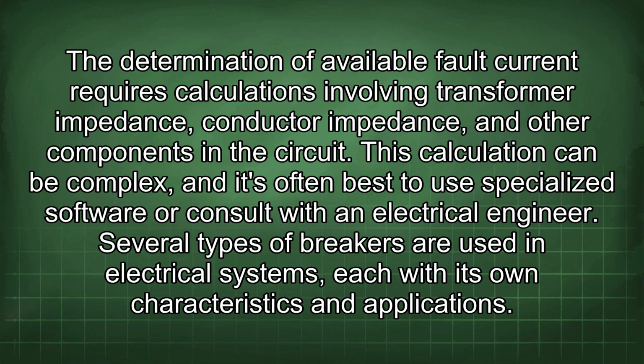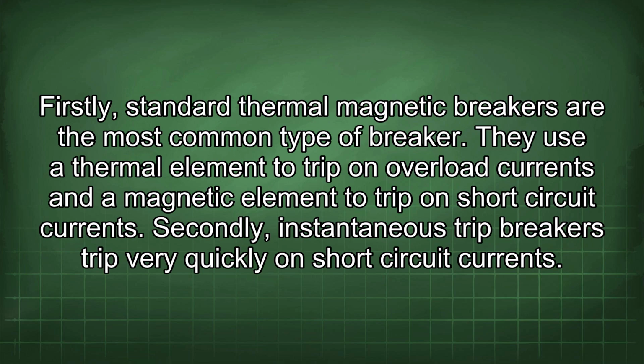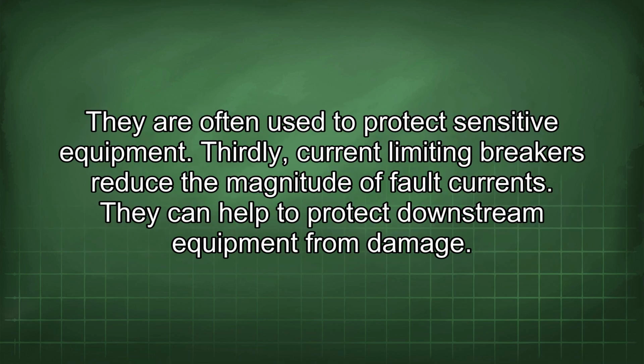Several types of breakers are used in electrical systems, each with its own characteristics and applications. Firstly, standard thermal magnetic breakers are the most common type of breaker. They use a thermal element to trip on overload currents and a magnetic element to trip on short-circuit currents. Secondly, instantaneous trip breakers trip very quickly on short-circuit currents. They are often used to protect sensitive equipment. Thirdly, current limiting breakers reduce the magnitude of fault currents. They can help to protect downstream equipment from damage.